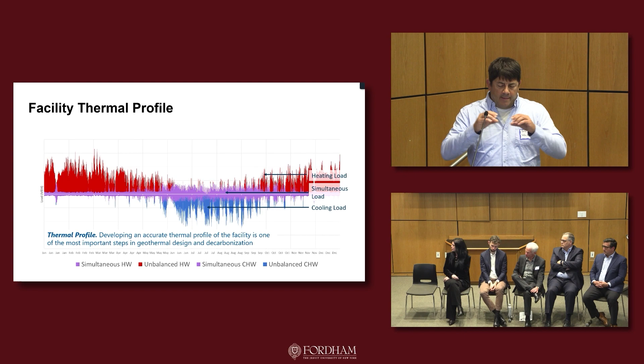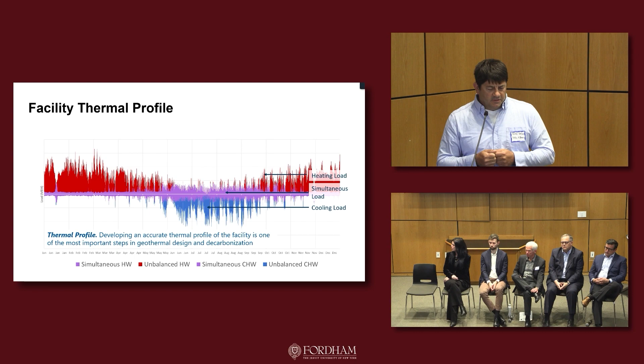This thermal profile drives all our economics and our design. If this thermal profile is wrong, everything's wrong, especially with heat pumps—we start oversizing them, and some heat pumps don't have very good turndown, maybe only a 50% swing, which causes major problems because the heat pump has to start and stop a lot. So we really must get better at developing thermal profiles and driving the accuracy of this, because it drives everything.